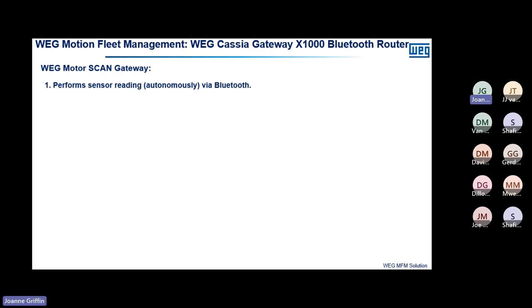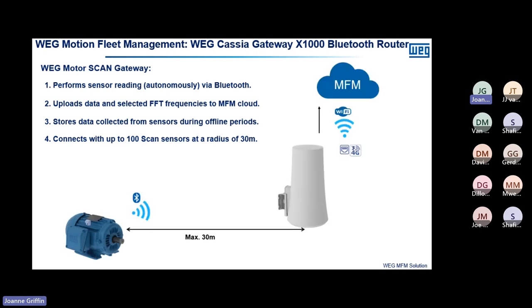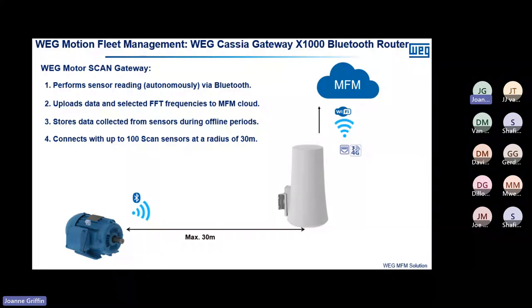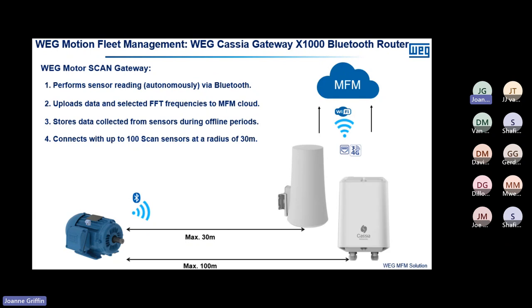Regarding the gateway: it polls sensors autonomously via Bluetooth and uploads selected Fast Fourier Transform frequencies to the MFM cloud — I'll show you some of those FFT frequencies later on. It stores data so that even during offline periods data is not lost. For the MotorScan sensor, the distance between the sensor and gateway should be about 30 metres line of sight, assuming no obstructions in between.